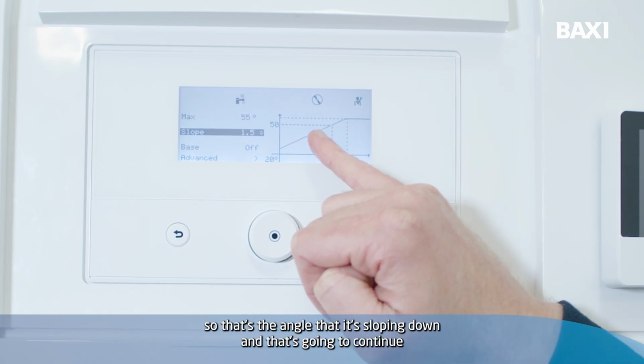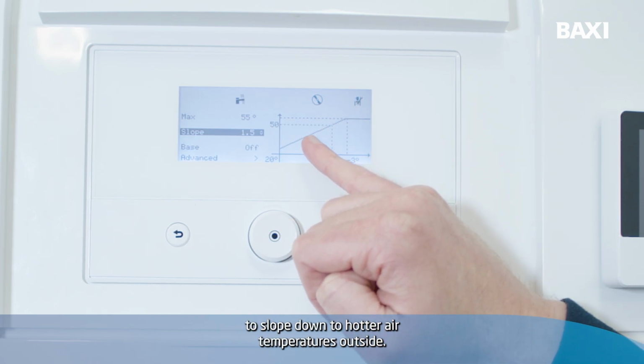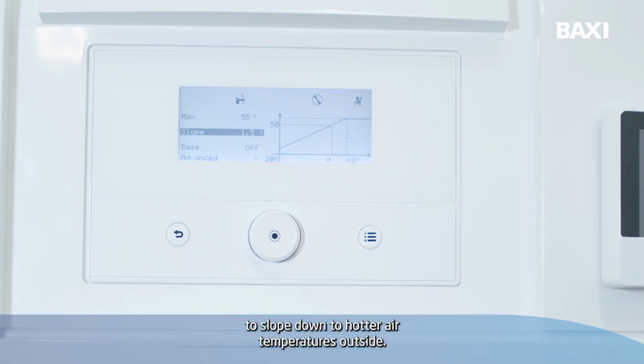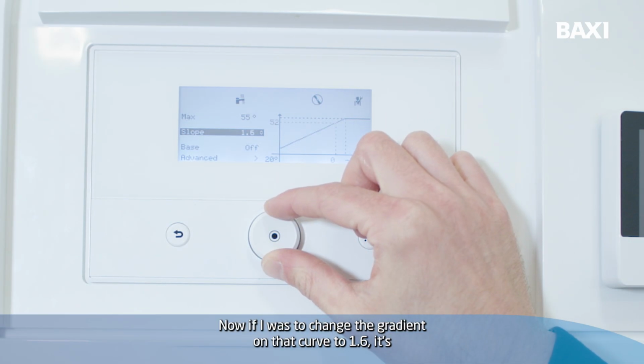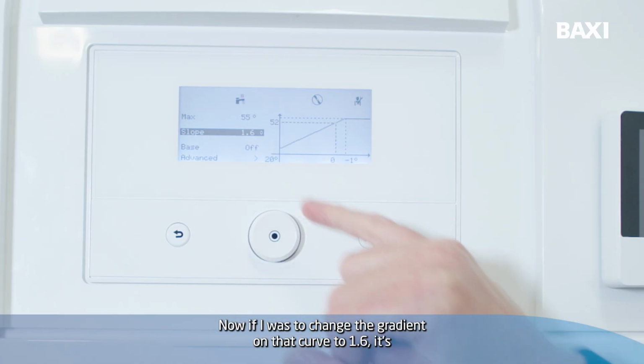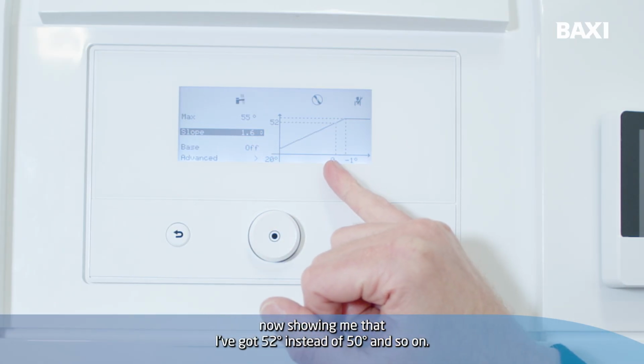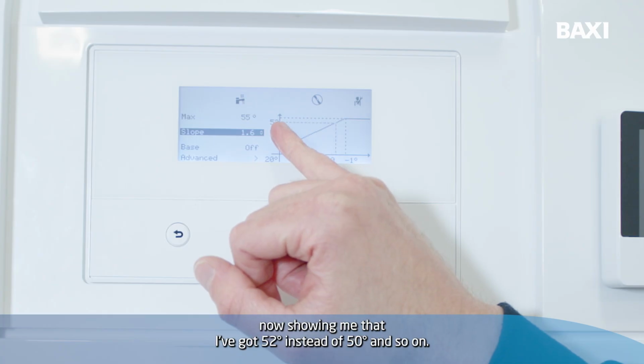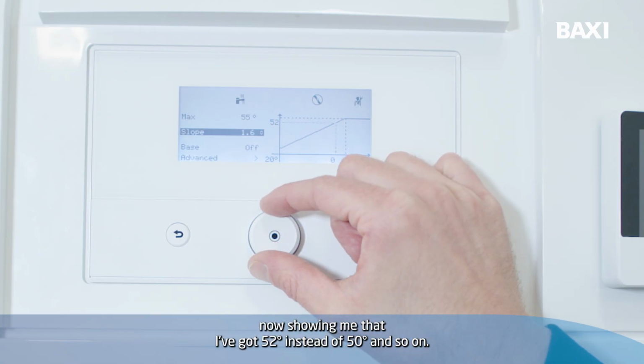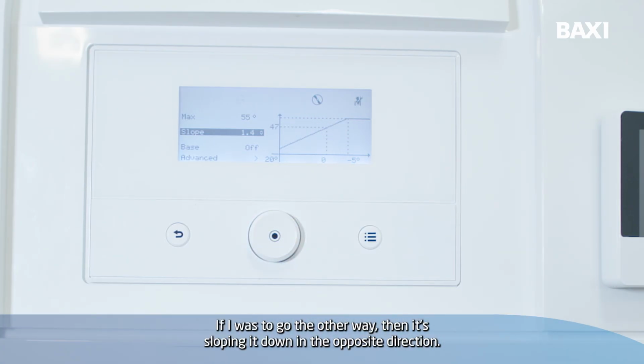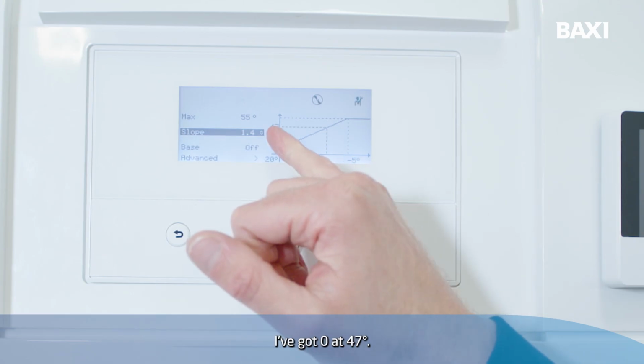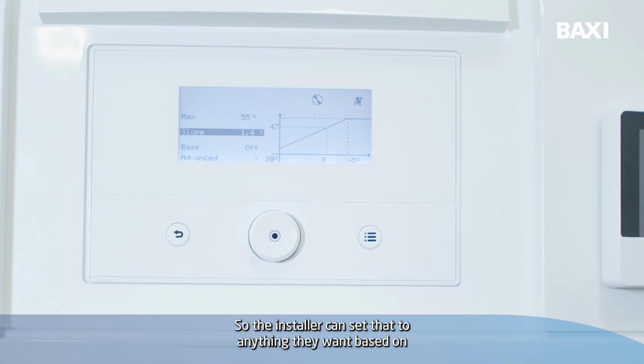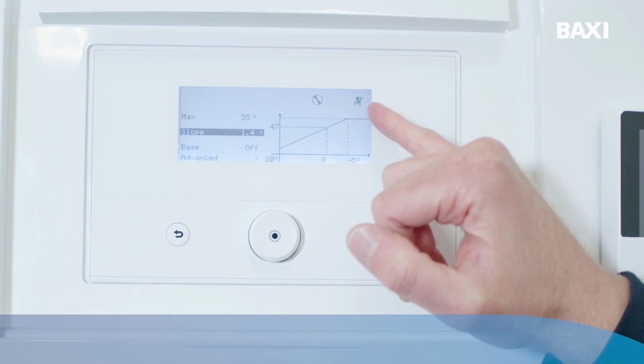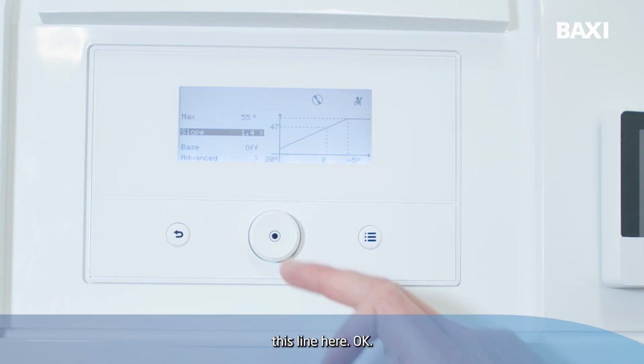So that's the angle that it's sloping down, and that's going to continue to slope down to hotter air temperatures outside. All right, now if I was to change the gradient on that curve to 1.6, it's now showing me that at 0, I've got 52 instead of 50, and so on. If I was to go the other way, then it's sloping it down in the opposite direction. I've got 0 at 47. So the installer can set that to anything they want based on this line here, okay?